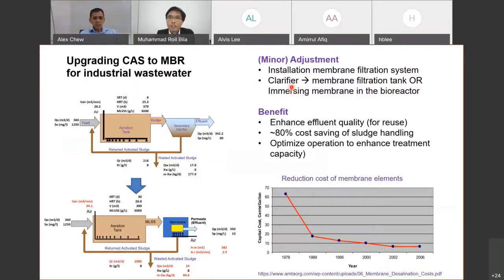What happened to the clarifier then? We can use the clarifier as a membrane tank, like in this example. Here we have a membrane tank. We just convert this clarifier into the membrane tank. We use it to place the membrane. Or we can use it for other purposes. We can increase the capacity of the treatment by combining the clarifier with the bioreactor and placing the membrane in the bioreactor. So this is how you actually increase the treatment capacity.